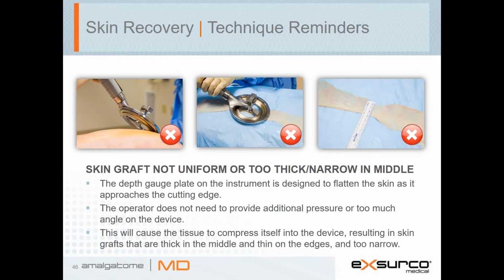Skin graft not uniform or too thick and narrow in the middle. The depth gauge plate on the instrument is designed to flatten the skin as it approaches the cutting edge. The operator does not need to provide additional pressure or too much angle on the device. This will cause the tissue to compress itself into the device, resulting in skin grafts that are thick in the middle and thin on the edges, and too narrow.